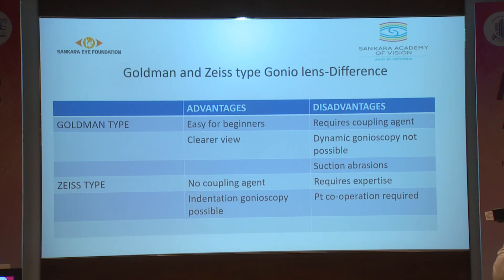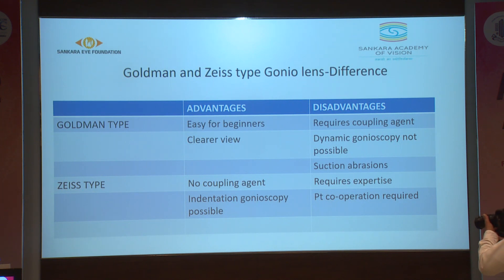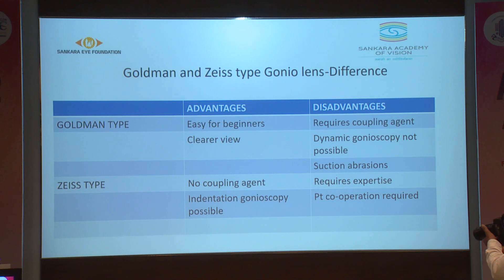Advantages of the Goldman gonioscope include being easy for beginners and giving a clearer view. However, disadvantages are that it requires a coupling agent, indentation gonioscopy is not possible, and suction abrasions can occur. With the Zeiss type gonio lens, no coupling agent is required and indentation gonioscopy is possible; however, it requires expertise and patient cooperation.